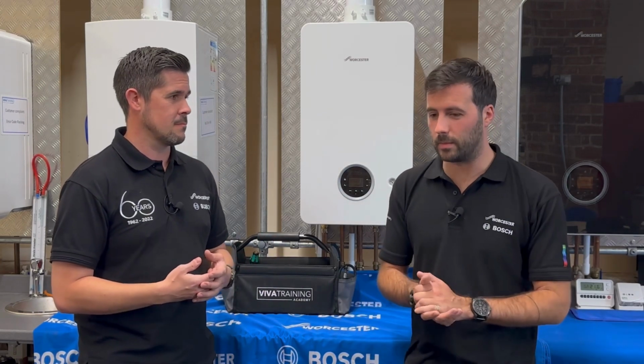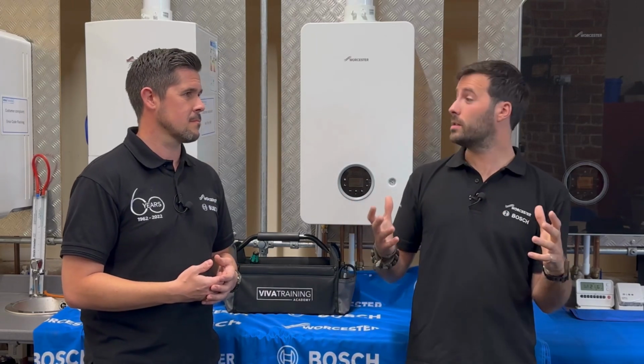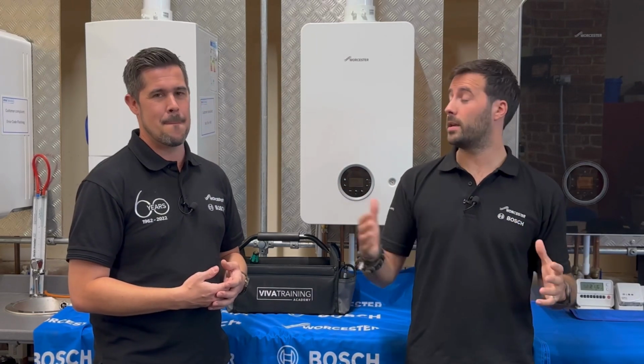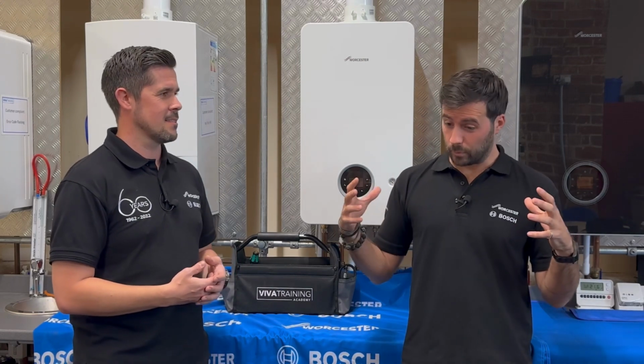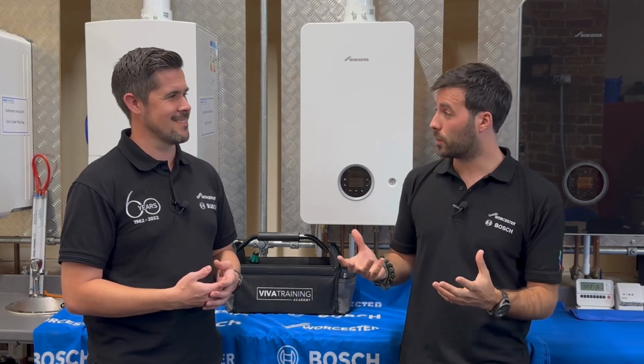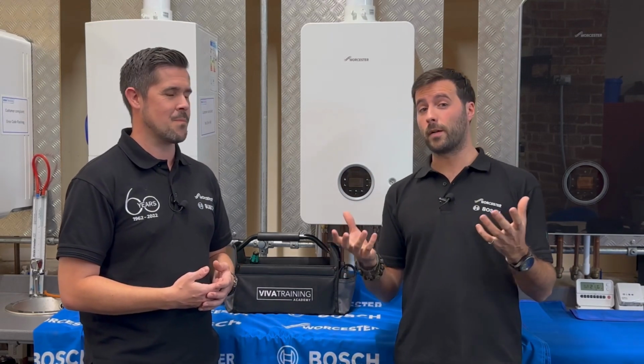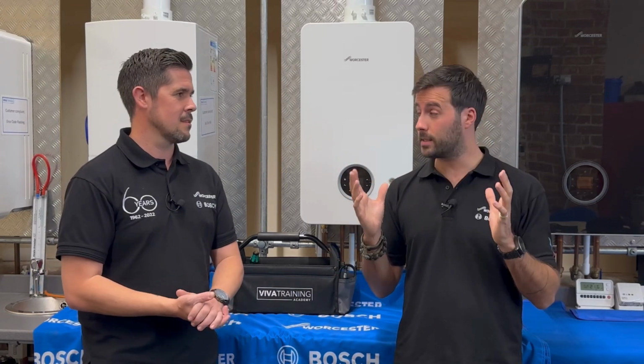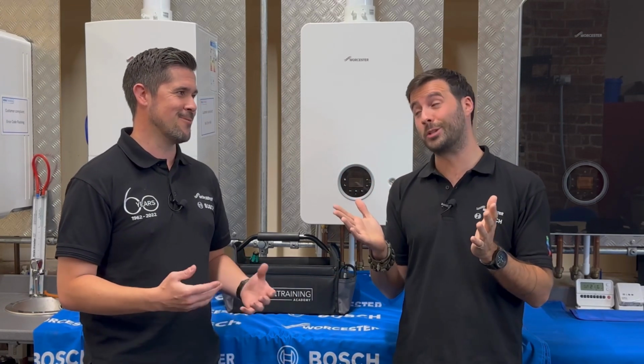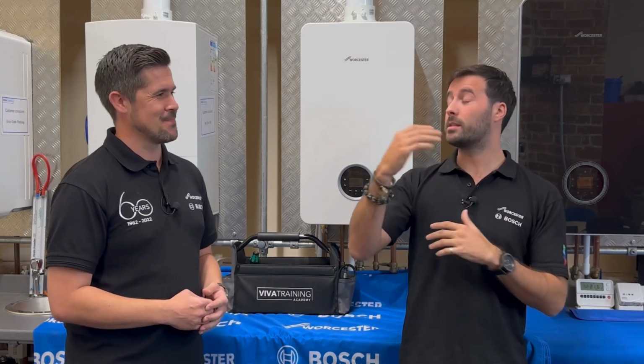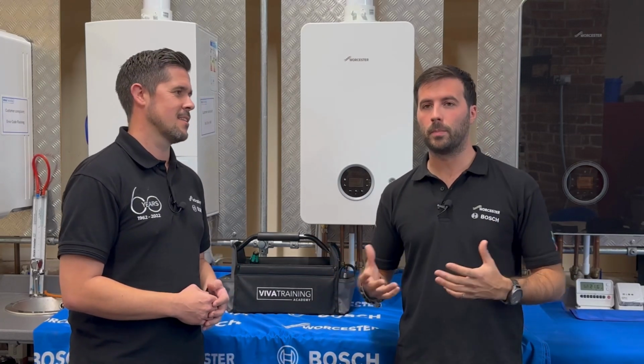Okay, cool, so basically the main one is efficiency. The lower you can operate a central heating system, the less resource or energy you're using to heat it up, or the boiler can behave more efficiently. Since 2005 we've had condensing boilers, but I'd hazard a guess that a lot of them don't condense very well because of the temperatures we're still using. When you look at a condensing boiler, you have something called the dew point, which you might have heard batted around a lot, but the dew point is at what temperature you need to drop the products of combustion for it to condense.